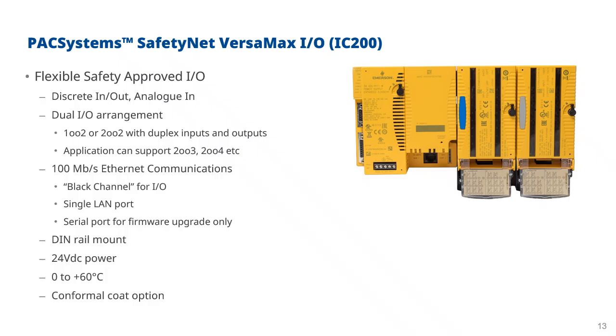So with this, mounting is DIN rail. It's 24 volt DC power again. VersaMax I/O is rated at 0 to 60 degrees C. And again, there's a conformal coat option if you are going to put these into environments where there are corrosive atmospheres.